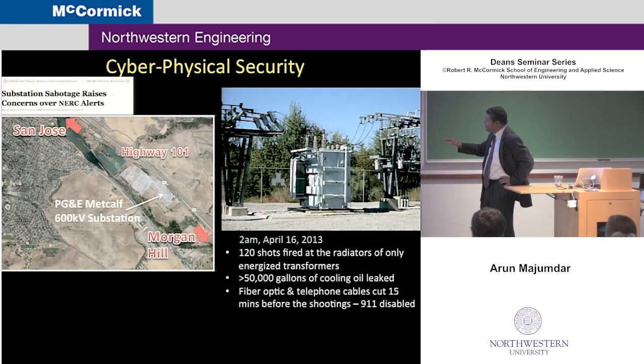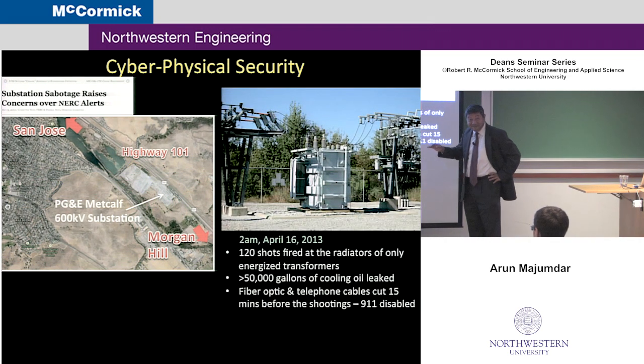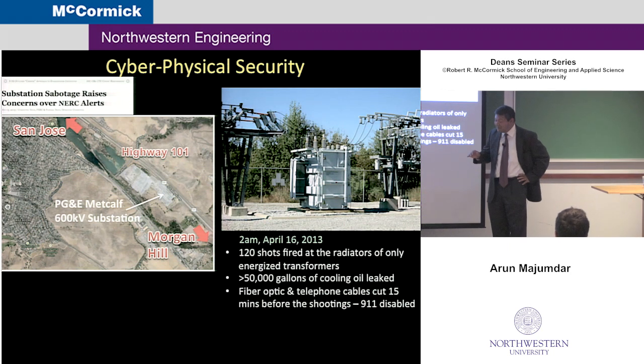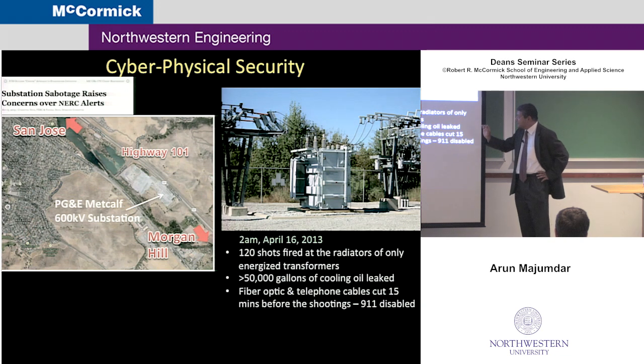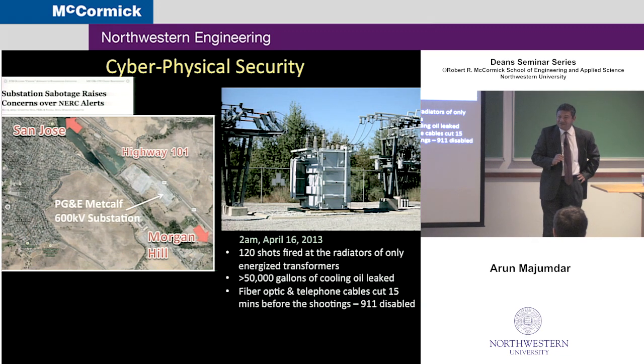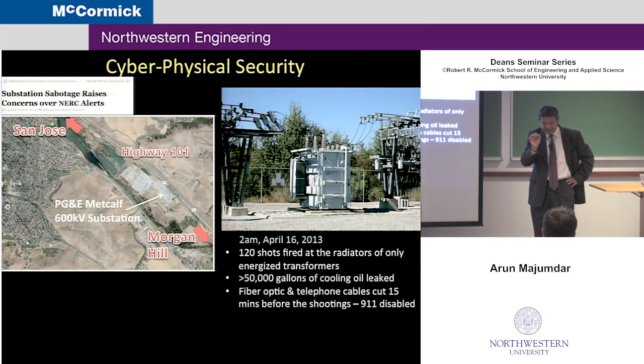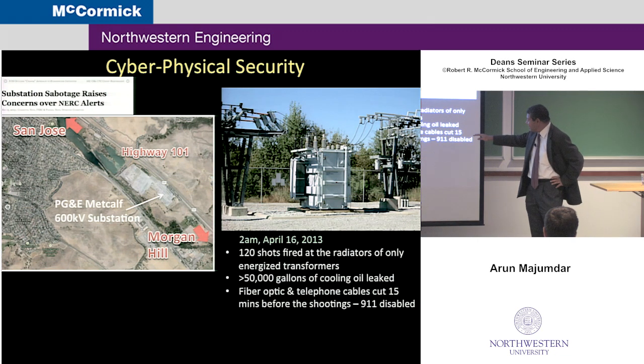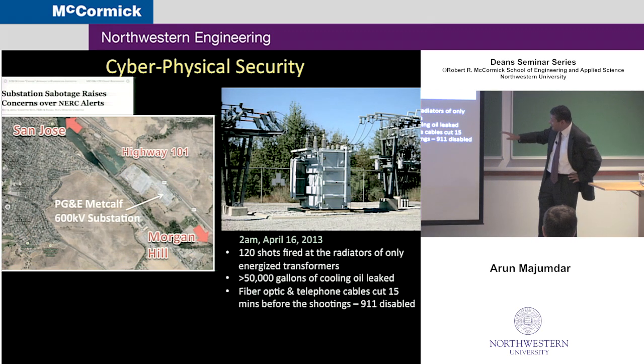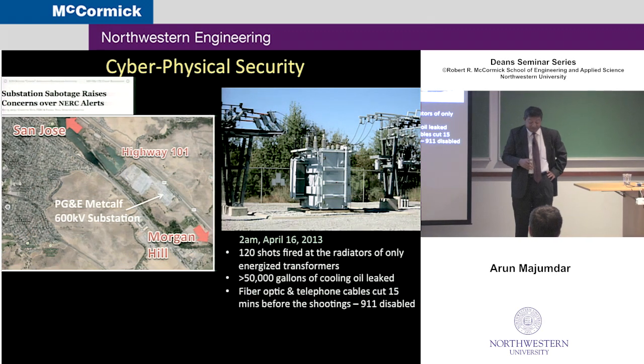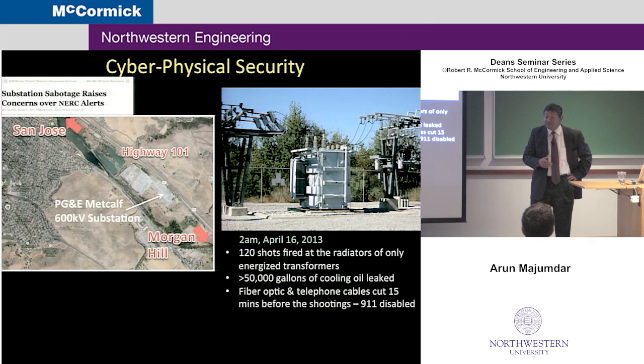At 2 a.m., people with guns came, and they probably had thermal cameras, because there were 120 shots fired. They knew exactly where to fire at the radiators of only the energized transformers, which are hotter. They shot those bullets right at the radiators because these transformers are cooled by mineral oil, so they leaked 50,000 gallons of mineral oil and tripped all these transformers. What's interesting is that 15 minutes before that, the same people had probably cut the fiber optic and telephone line so that 911 was disabled.